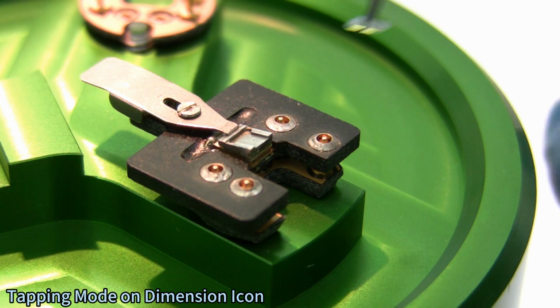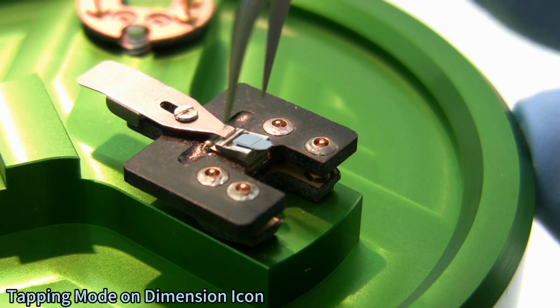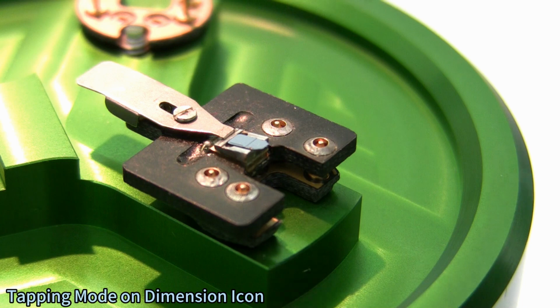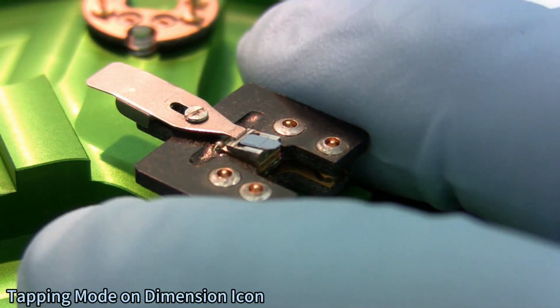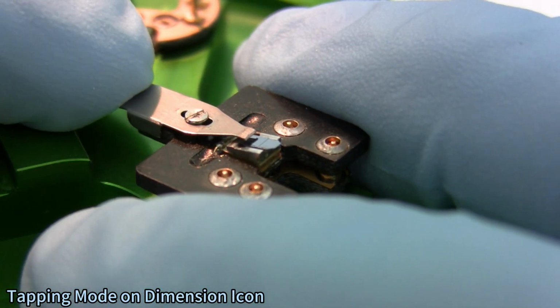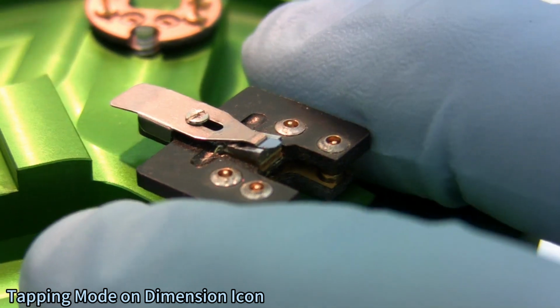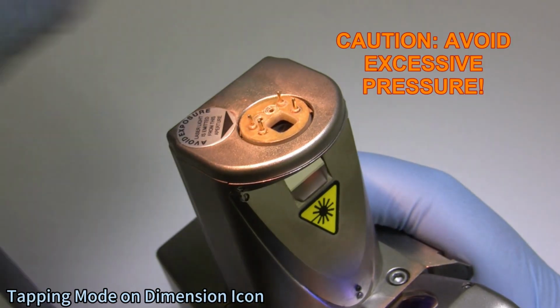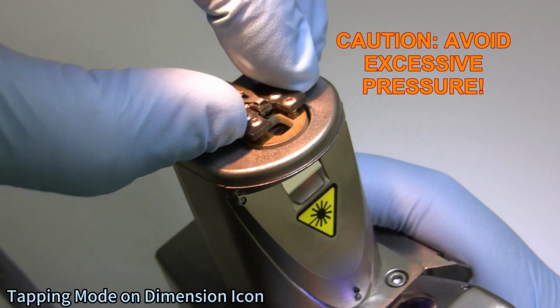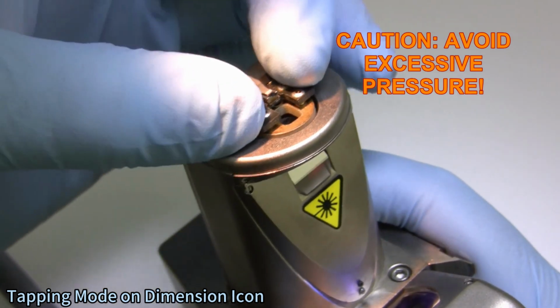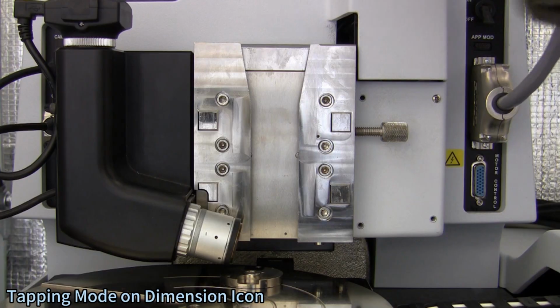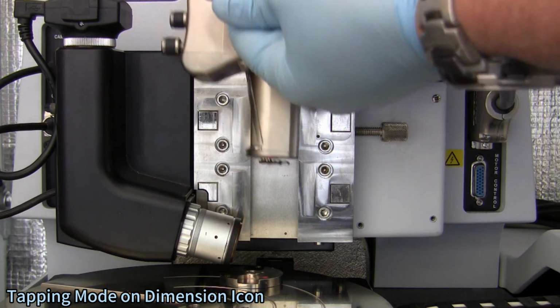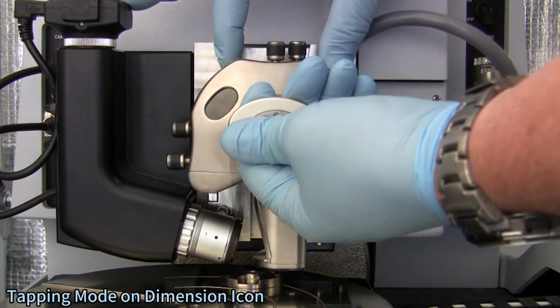As with all modes of AFM, the procedure begins with the installation of the probe into the probe holder. Use a pair of tweezers to load a probe into the holder. Then move the spring clip over the probe chip to hold it in place. Place the holder onto the 4 pins at the end of the scan head. Take care to avoid forcing the holder onto the pins. Place the scan head back into the dovetail cradle and secure it.